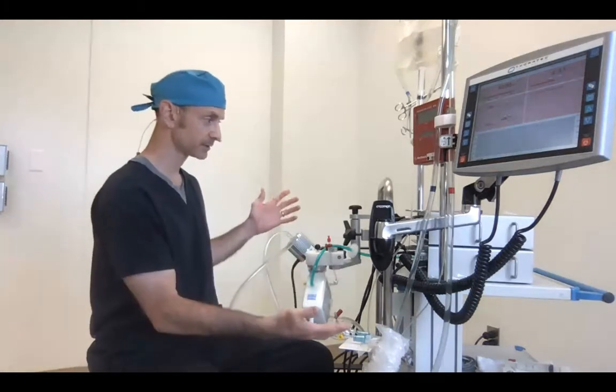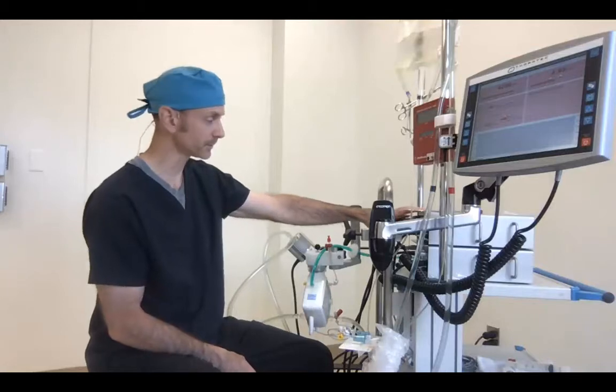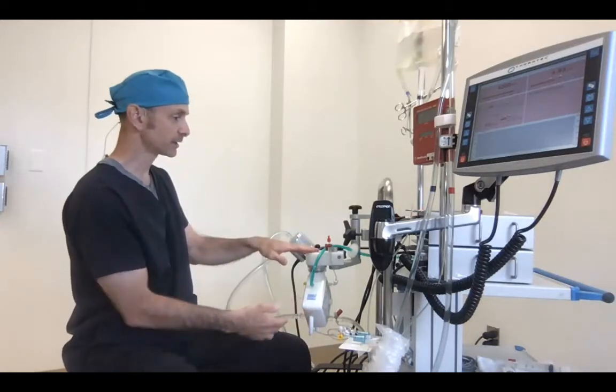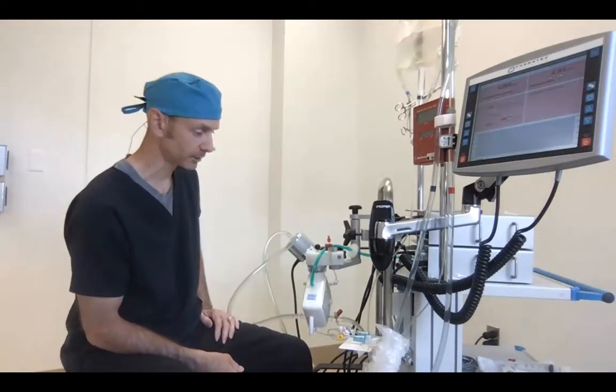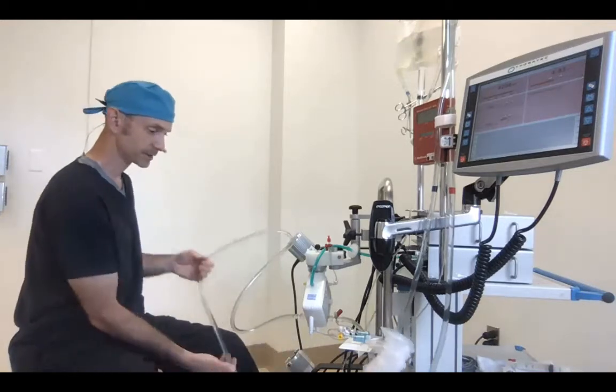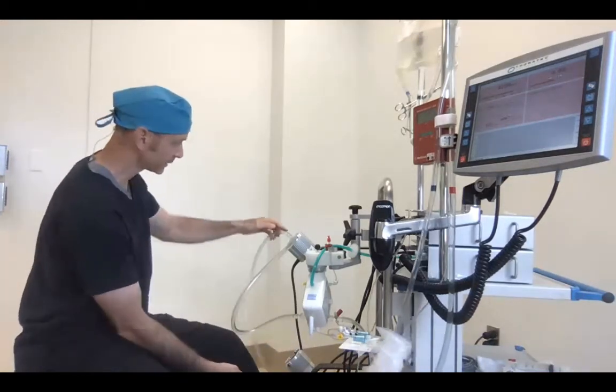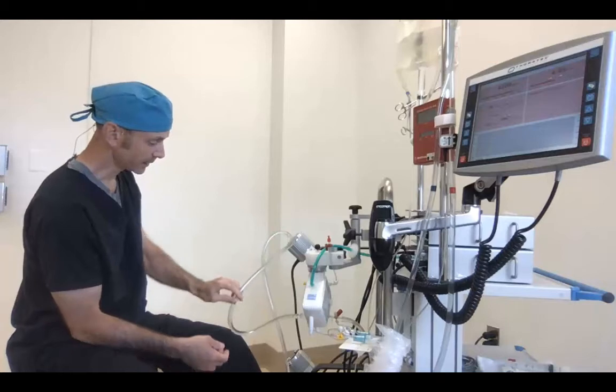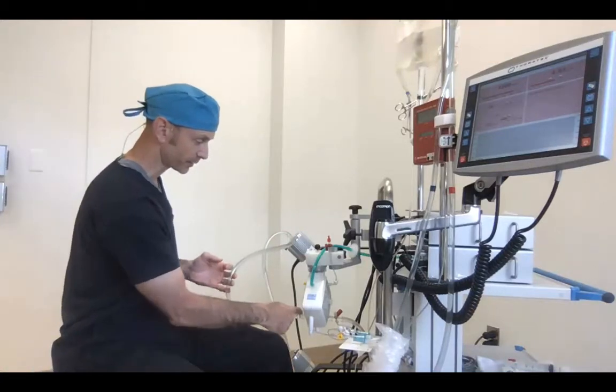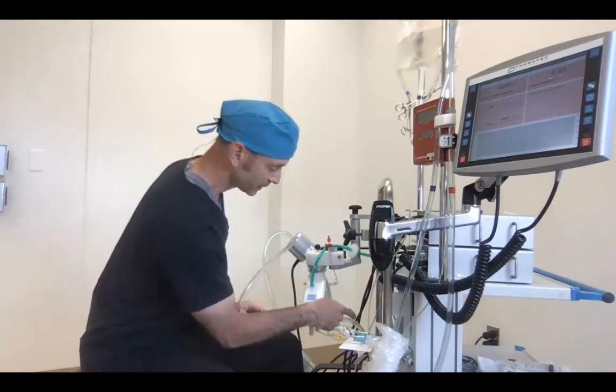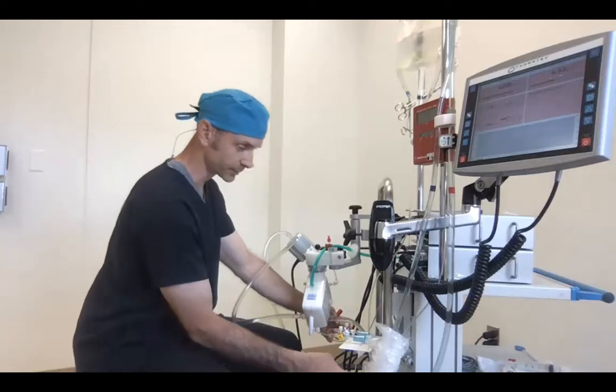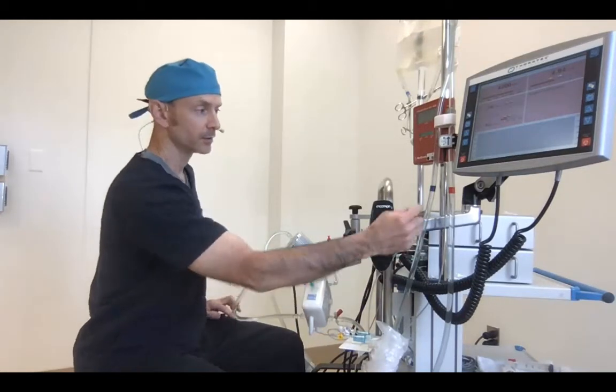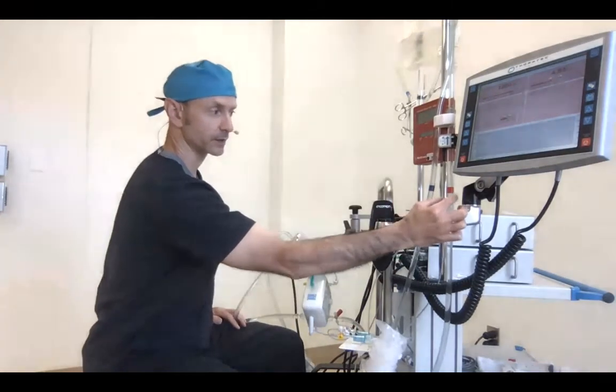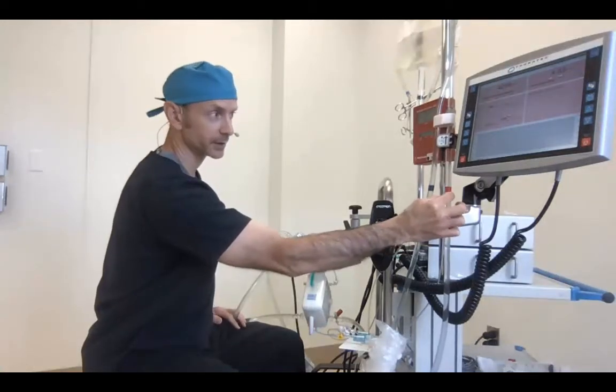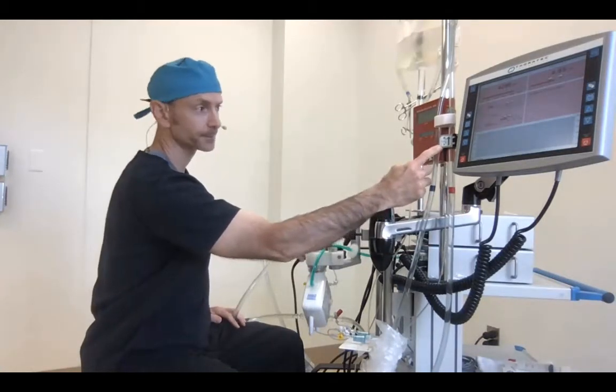We're using the Centrimag system here. We have the Quadrox oxygenator, and it's a conventional ECMO circuit all around this, with a venous line that comes down to the inlet of the Centrimag pump. The outlet of that pump then goes into the pre-membrane side of the Quadrox, and the post-membrane side of the Quadrox continues up. We have a blue stripe on our venous line, and a red stripe on the arterial line, and the flow probe right there.